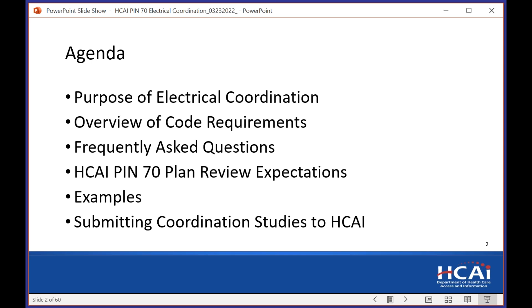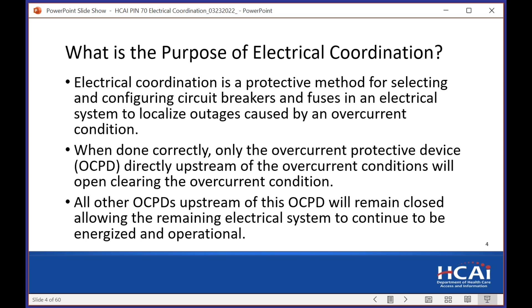So let's take a look at the purpose of coordination. What's the purpose of electrical coordination? Well, electrical coordination is a protection method for selecting and configuring circuit breakers and fuses in an electrical system to localize outages caused by an overcurrent condition. When you do it correctly, the outage is localized to the nearest overcurrent protection device upstream. All other overcurrent protection upstream of this device will remain closed.